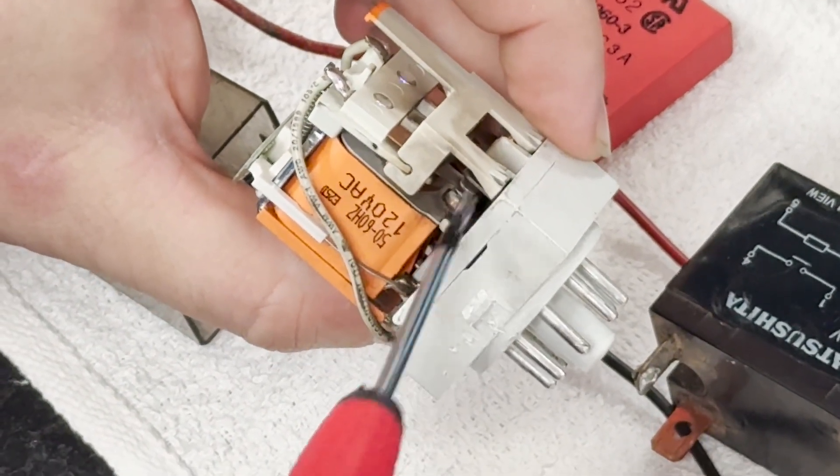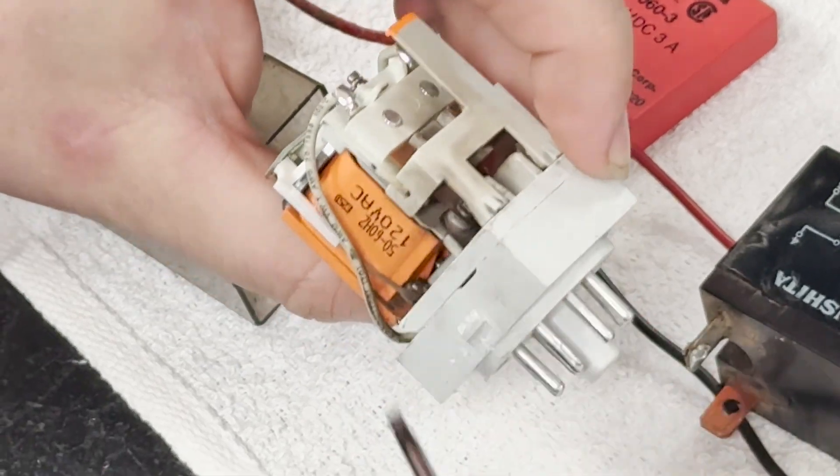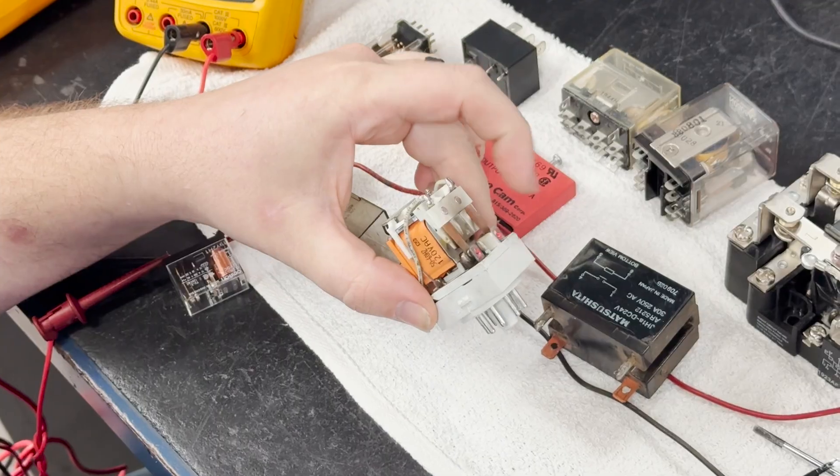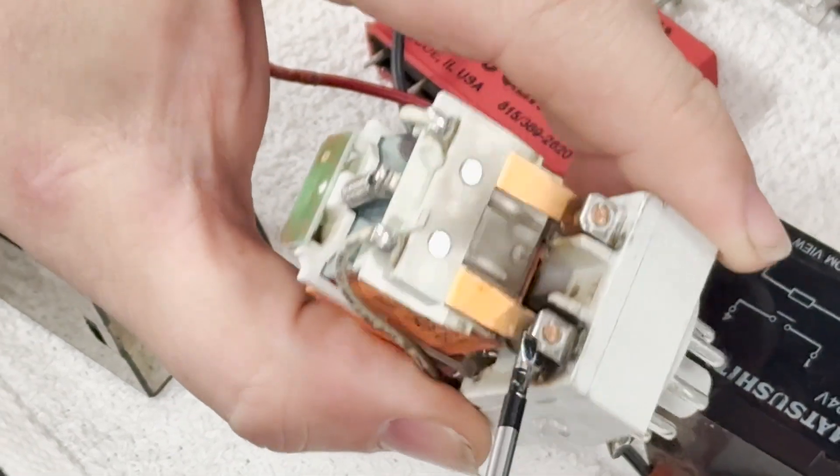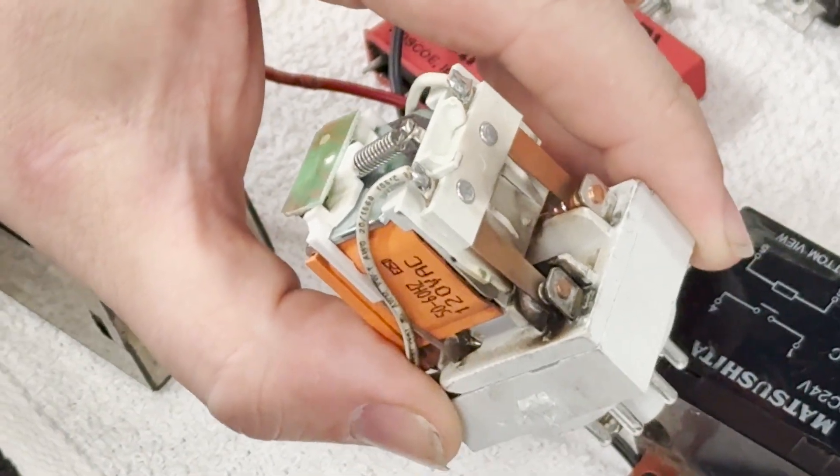However, you can see a severe amount of carbon that has accumulated on this set of contacts, and what this has caused is that these set of contacts can't make a proper electrical closure because of how degraded it is.